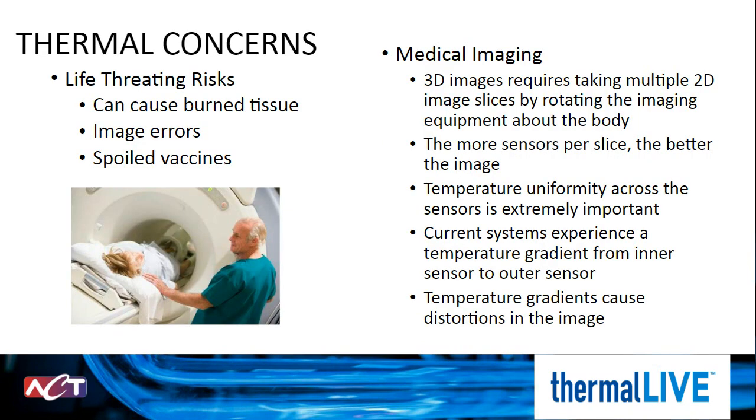Now, the medical industry has a very real risk when it comes to thermal challenges, primarily because the thermal issue has the potential to be life-threatening. So many of the surgical devices and the surgical tools used are rated until they hit about 109 degrees Fahrenheit. Now that's a temperature that will burn tissue. So think about it this way. A surgeon is using a drill to operate on a patient. The small motor in the drill continuously heats up during use, but after an hour of operation, the drill has reached that 109 degree Fahrenheit threshold.